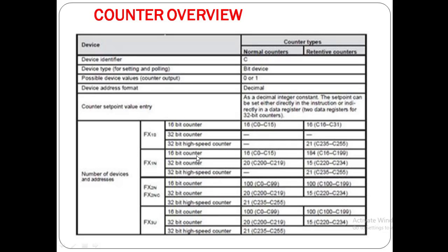Counter overview: there are different counters available — normal counters, retentive counters, and high-speed counters. Counter is denoted with C, device type is bit device, and device address format is decimal. Counter set point value entry is as a decimal integer constant; the set point can be set either directly in the instruction or indirectly in a data register — two data registers for 32-bit counters, one register for 16-bit counters.